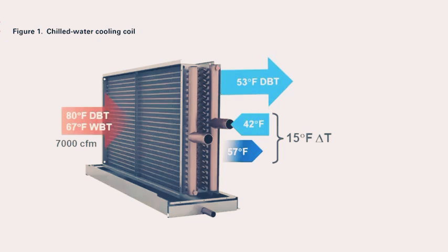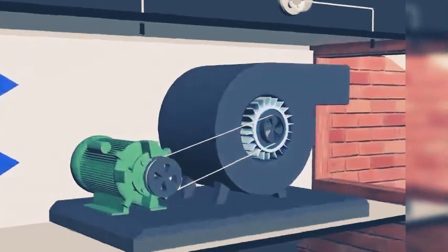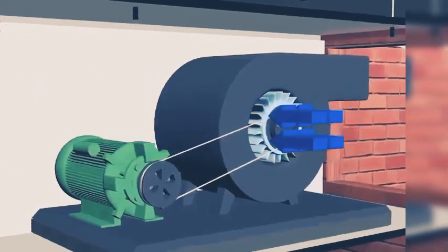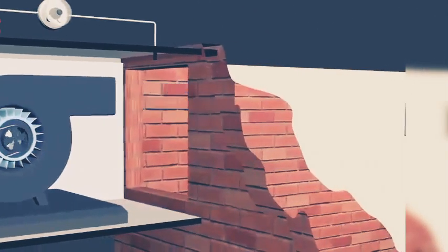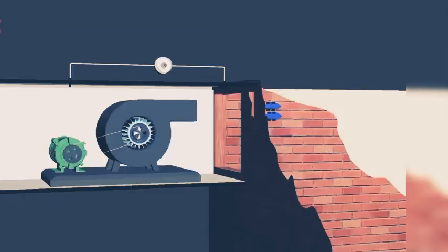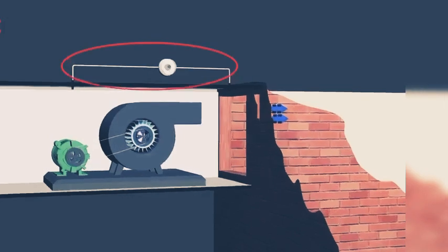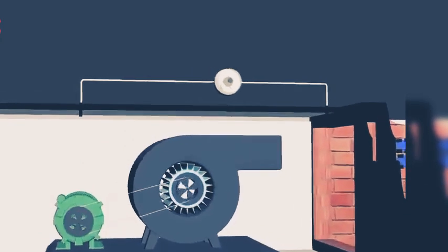The fan coil unit will contain a purpose-designed drip tray installed below the coil with a drain connection for this purpose. Normally a drain pipe is connected to this drain connection, which transfers the condensate to the nearest floor drain. The nicely cooled and non-humid air is then transferred to the space through the fan to create a comfortable environment. The speed of this fan is controlled from the space thermostat by simply increasing or decreasing the fan speed. Another pressure differential transmitter could be installed along the fan and connected to the BMS system to give an indication of a damaged belt in case of zero pressure difference.